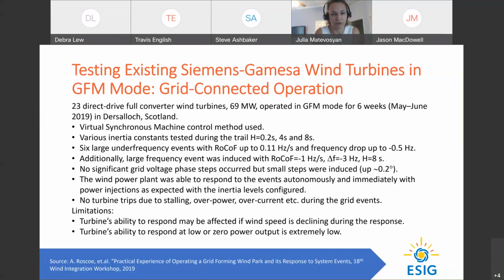As Jason mentioned, grid forming controls can be implemented in different ways. To be fair, all of the applications that I'll be talking about today went for the virtual synchronous machine control method. That mainly has to do with synchronous machine behavior being more familiar, and trying to replicate that with grid forming inverters. They tested different inertia constants. In virtual machine mode, a swing equation is programmed in, and the inertia constant can be changed. Depending on the storage or energy buffer available behind the inverter, there is some flexibility in changing the inertia constant. So they tried different inertia constant settings.